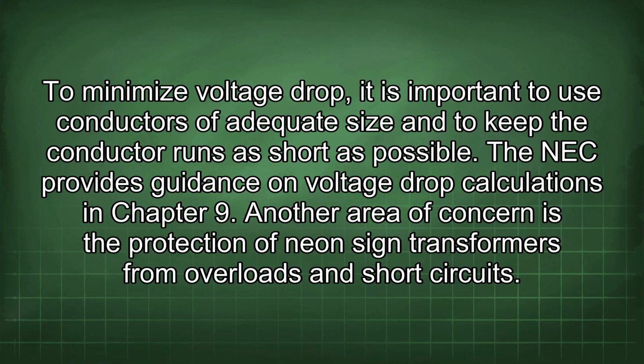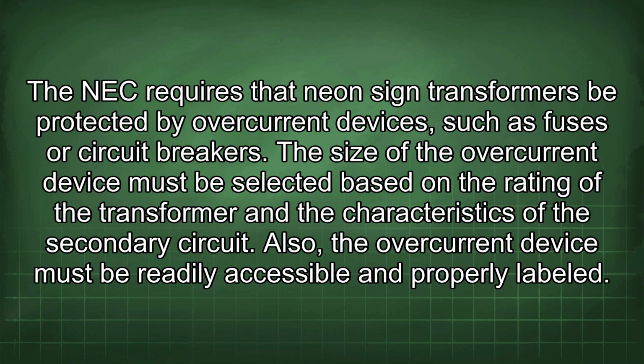Another area of concern is the protection of neon sign transformers from overloads and short circuits. The NEC requires that neon sign transformers be protected by overcurrent devices such as fuses or circuit breakers. The size of the overcurrent device must be selected based on the rating of the transformer and the characteristics of the secondary circuit. Also, the overcurrent device must be readily accessible and properly labeled.